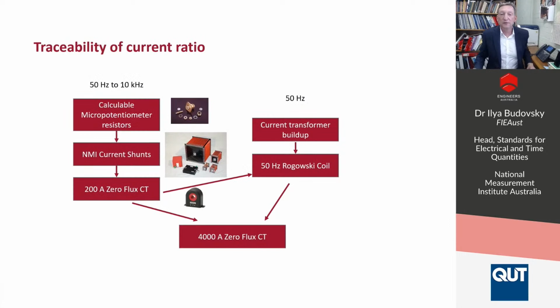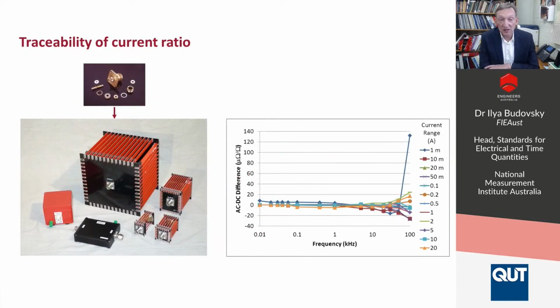So we've relied heavily on the history of our work to provide traceability to these measurements. And that comes from calculable resistors through special current shunts that we've developed. And all of this is used first to calibrate a 200 amp zero flux transformer.